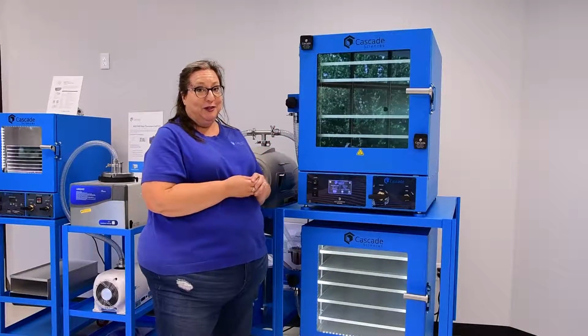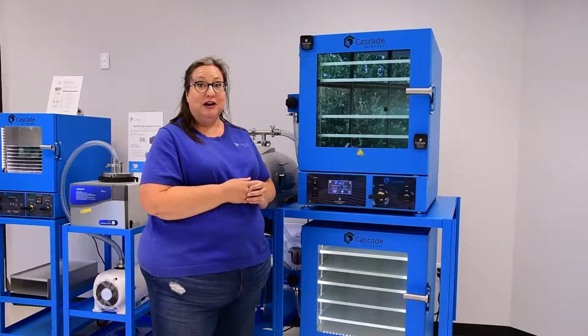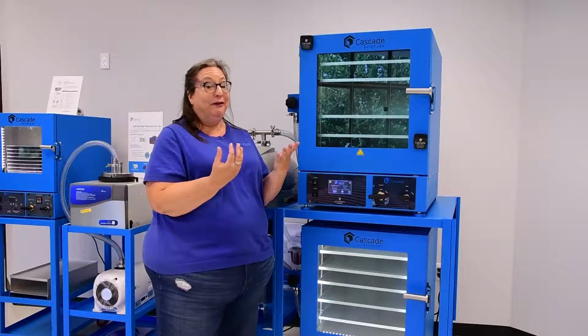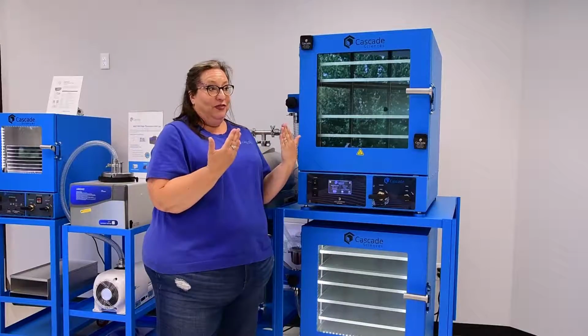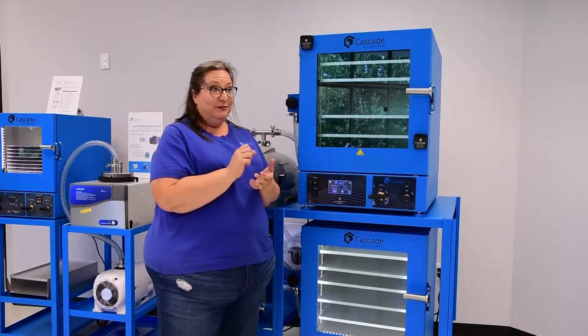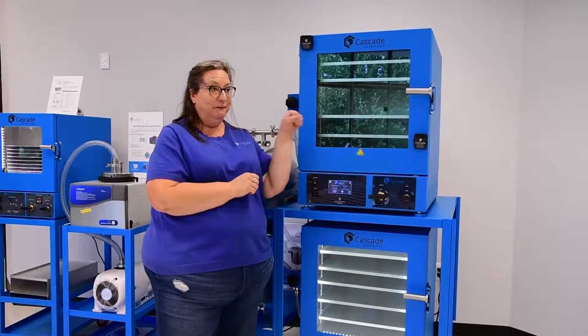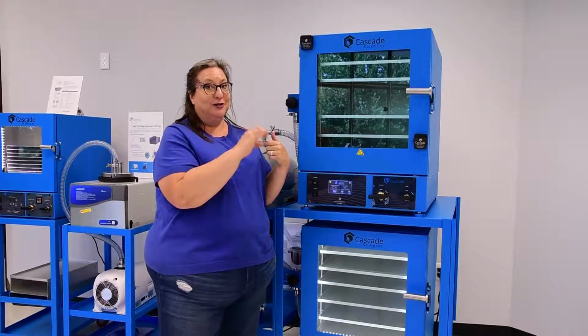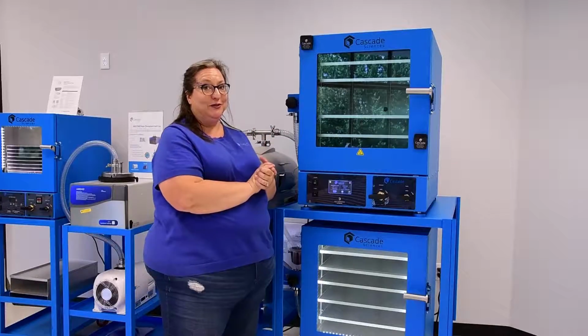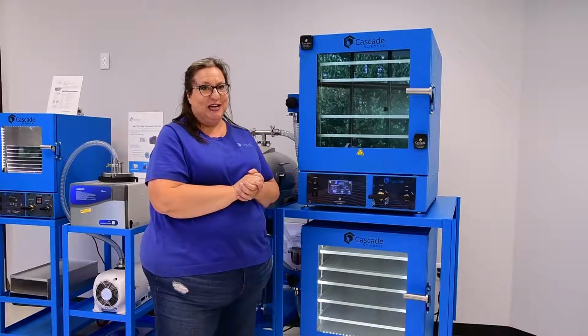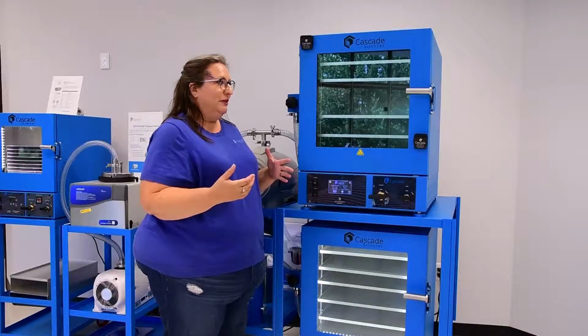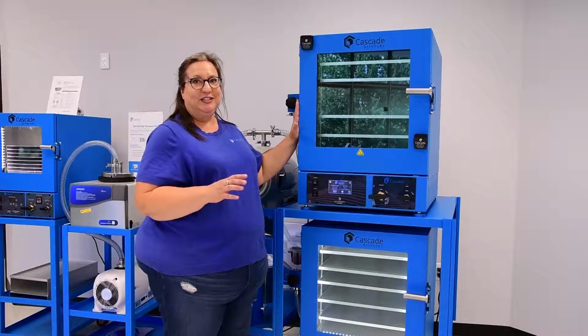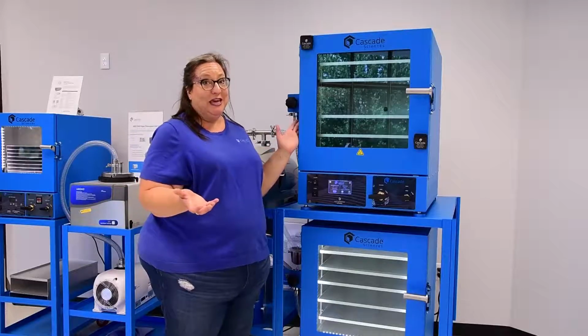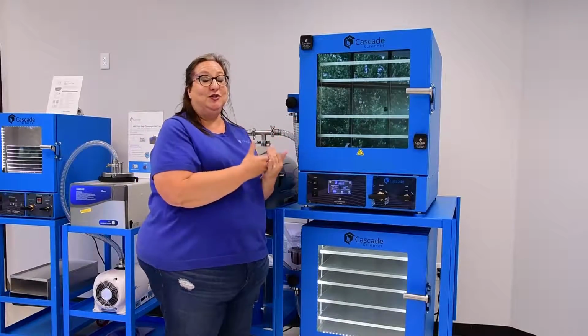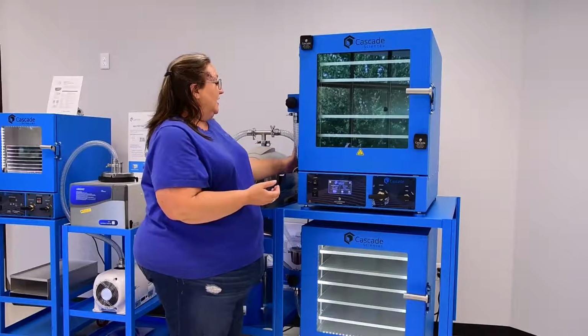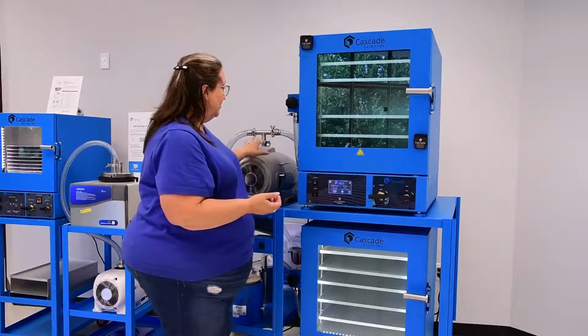Some manufacturers saw that we had a KF25 accessory port on our oven, so they put one on their oven too, but surprise, if you took off the side wall and looked inside, it was just 3/8-inch silicone tubing after the KF25 port. So for the benefit of the customer, it looked like a KF25 port, but the plumbing was just their standard crappy rubber tubing plumbing, which we would never use. This has all interior stainless steel plumbing, which you can't see, but you rely on us to do the right thing when you can't see it. So we have all this plumbing on the outside. It goes straight to the pump.